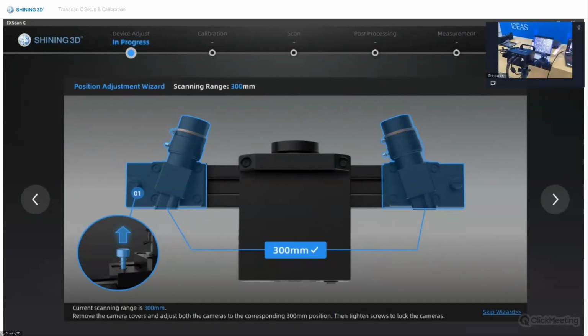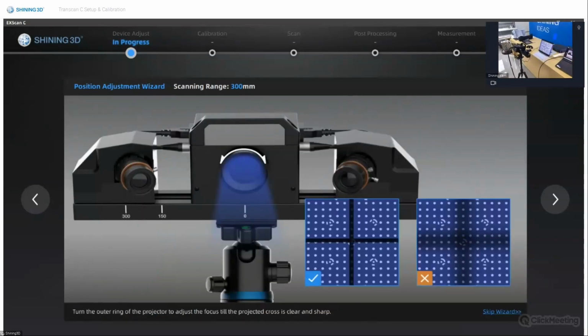And make sure both cameras are on the 300 level, 300 range. Okay. And next, we're going to focus the projector. So you see there is a ring outside the projector. That's how you turn it, how you adjust the projector focus. A good focus is to make sure the projected pattern, the cross, is sharp and clear. Like this. Should be good. Okay.